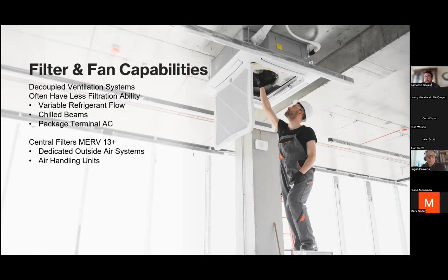And then packaged terminal air conditioners, the ones that just simply go into the wall. The way that those work, with some of the major manufacturers, the outside air actually bypasses the filter, where the filter just recirculates the air into and from the space and then pushes it back into the room. And so that outside air just bypassing the filter right there, that's just going to pull whatever smoke is outside. It's just going to pull that right into the space. So just a caution on packaged terminal air conditioning units. I know that they're a very cost-effective solution that I see used a lot, whether it be student housing or multifamily housing, but just note that there is a concern of not being able to filter the outside air very well.